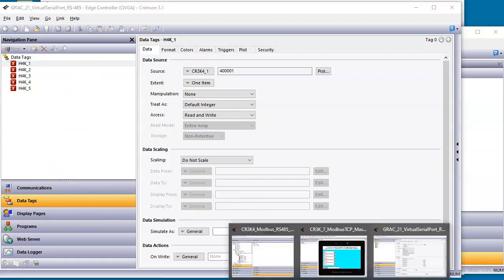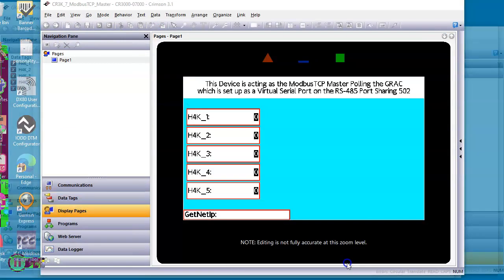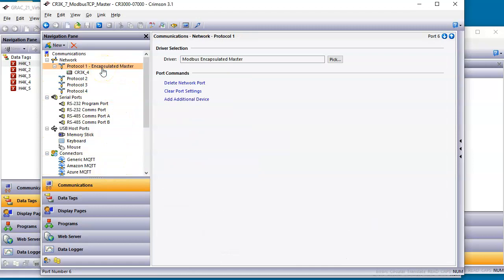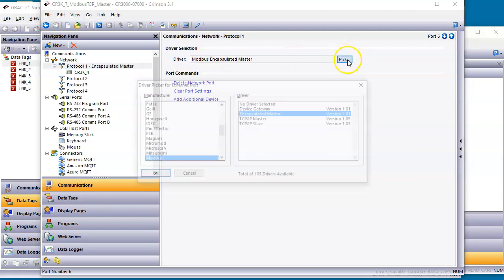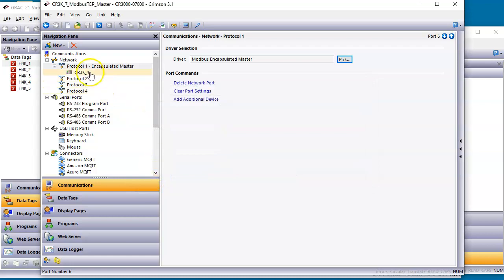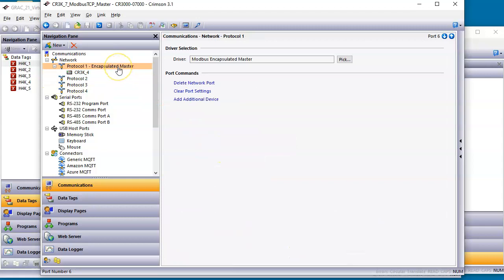And then the master case, I'm using a seven inch screen to act as a master over Modbus TCP. I'm doing something different here on the Modbus side. I'm using an encapsulated master driver, not the normal master, but because I'm doing this 485 to Ethernet, I'm using this encapsulated master. If I click here, there's the device, there's the IP address of the GRAC. Notice the port number. Nothing else is different other than I'm using this particular driver as an encapsulated master.